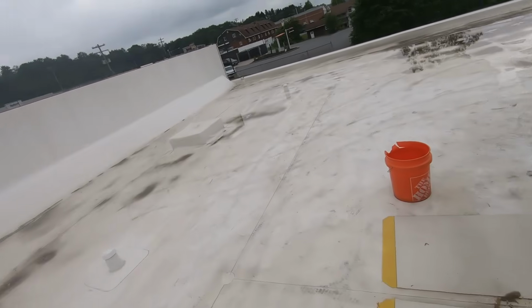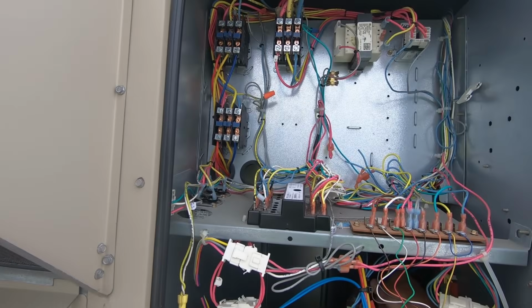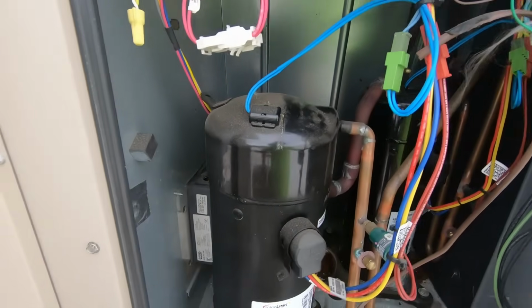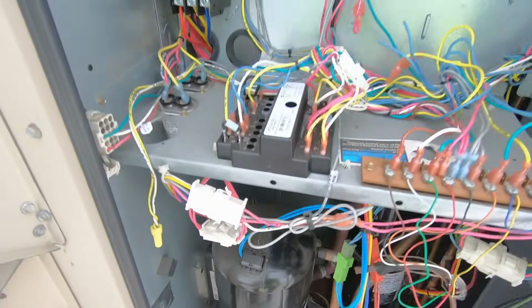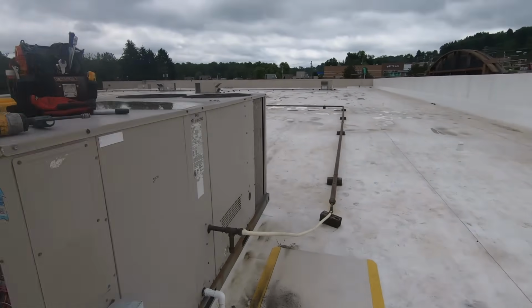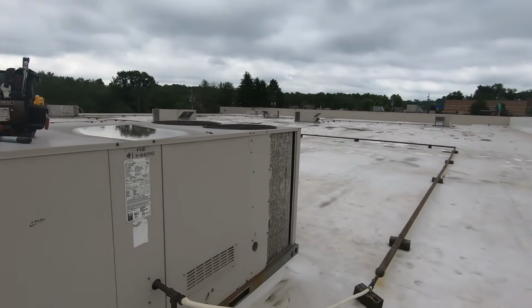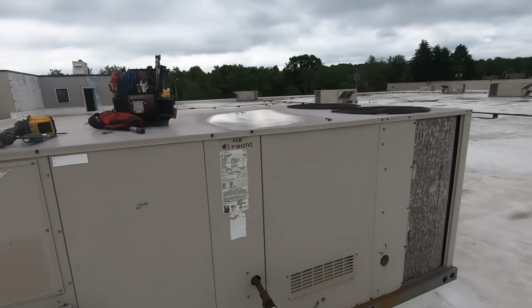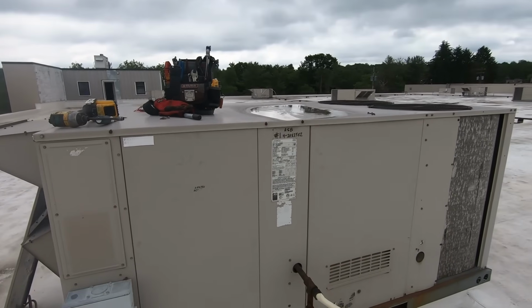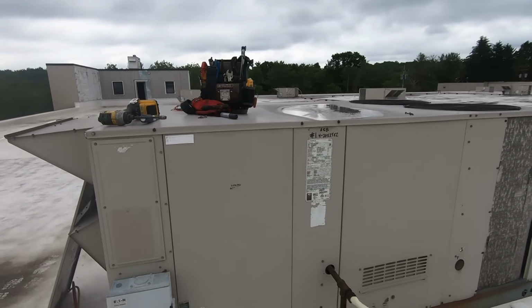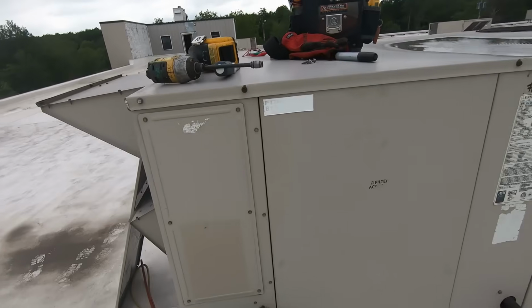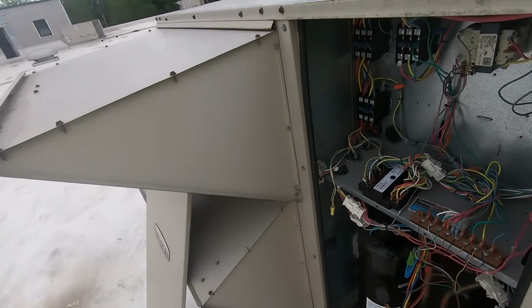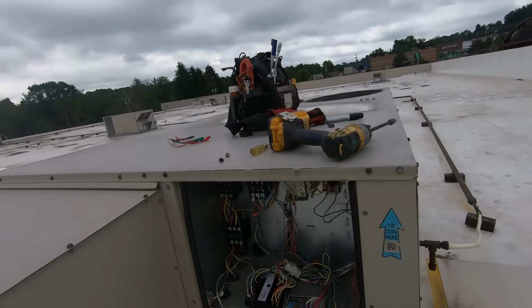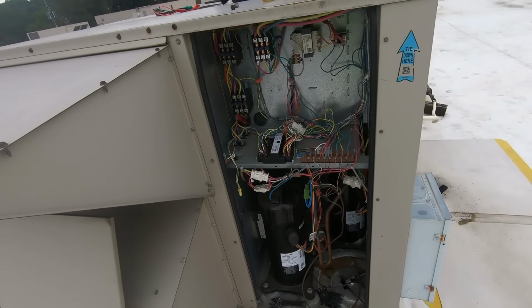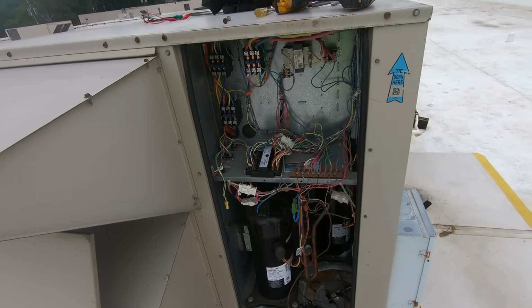I'm moving on. I don't see anything crazy here. This is a service call. Moving on from this guy, and gonna hit them all. Get all the relevant information, belts, filters, coil cleanings, contactors if it's needed, and basically come back and do a preventative maintenance. He said there's been no preventative maintenance done. The air filter was dated sometime in 2024.